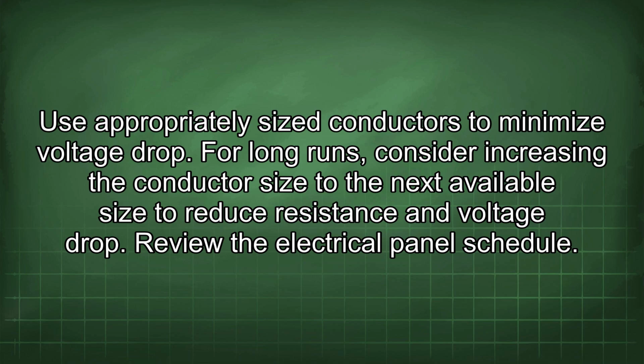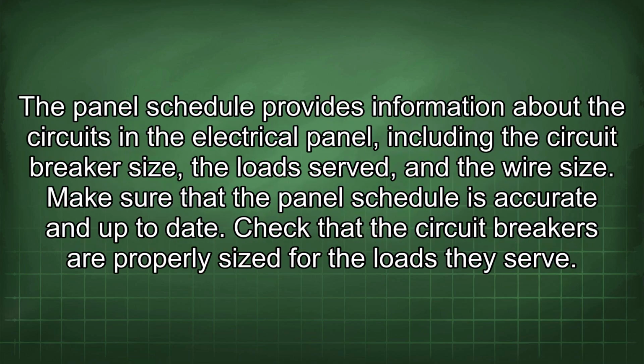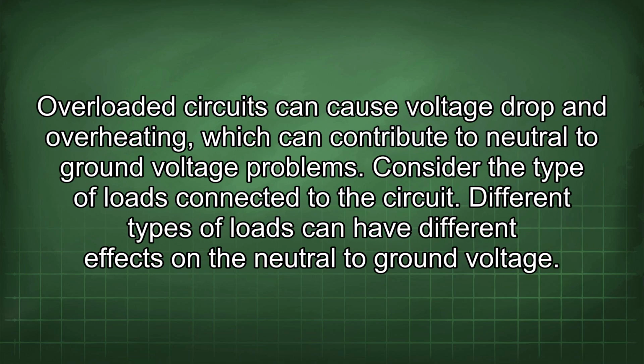Review the electrical panel schedule. The panel schedule provides information about the circuits in the electrical panel, including the circuit breaker size, the load served, and the wire size. Make sure that the panel schedule is accurate and up to date. Check that the circuit breakers are properly sized for the loads they serve. Overloaded circuits can cause voltage drop and overheating, which can contribute to neutral to ground voltage problems.